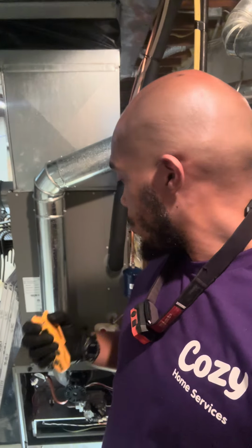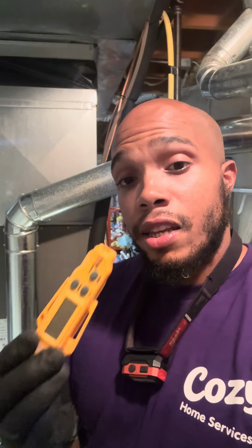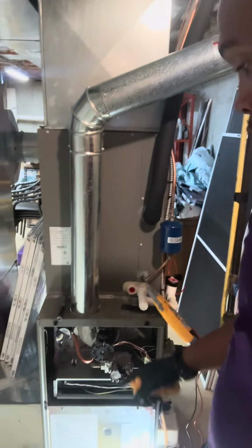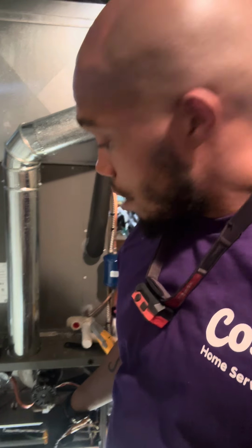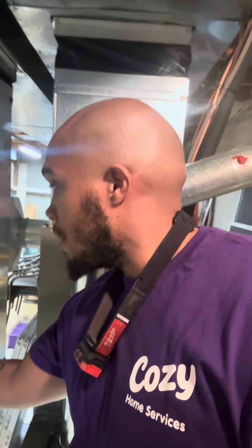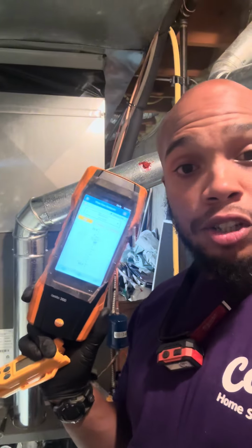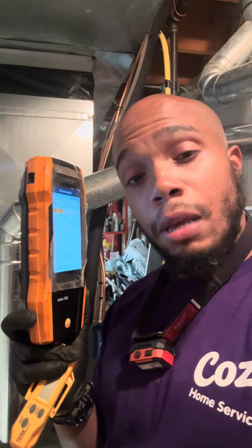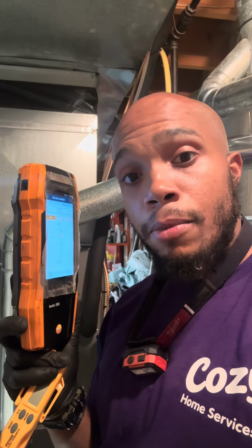All right, so now we're gonna go ahead and test the system. When you are testing a fossil fuel appliance, especially a gas furnace, the main 3 things I'm looking for is temperature split. I'm looking for the amperages on these motors. I'm checking the flames to see the integrity. And I'm also doing a combustion test using my combustion analyzer. And this bad boy is gonna tell me everything I need to know about how the system's operating. So let's get everything hooked up and then we'll go ahead and kick it off.